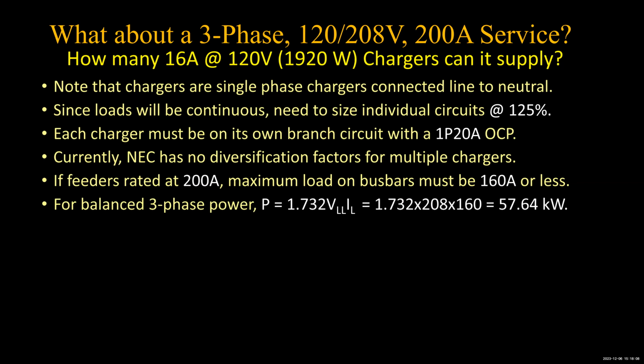So let's say we got a balanced three-phase system. That means the power being delivered is 1.732, square root of 3, times the line-to-line voltage times the line current. And if it's balanced, then the line currents are going to be the same. So this then tells us the total power available: 1.732 times the 208 volts line-to-line times 160 gives 57.64 kilowatts available for charging.